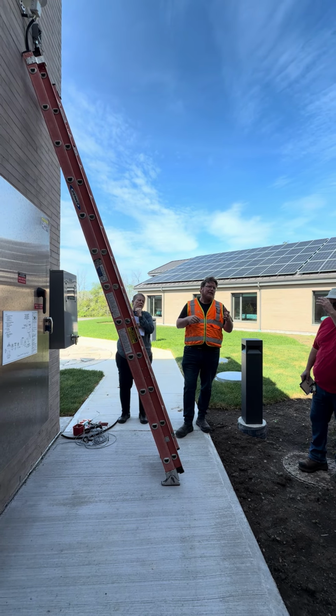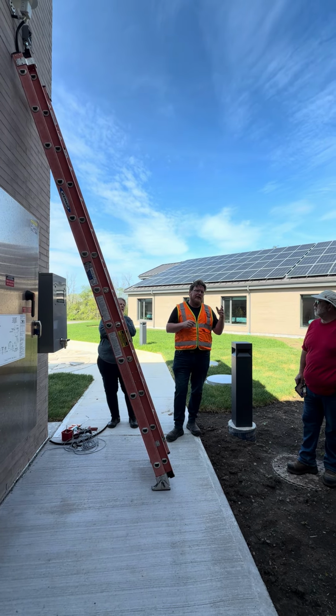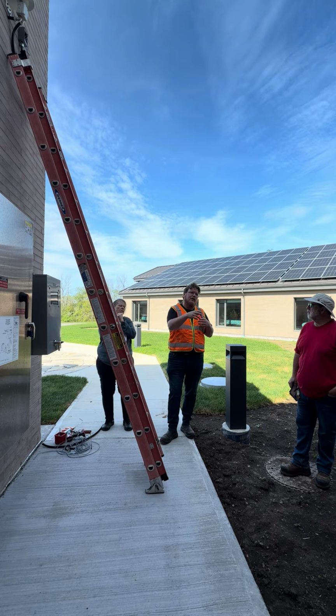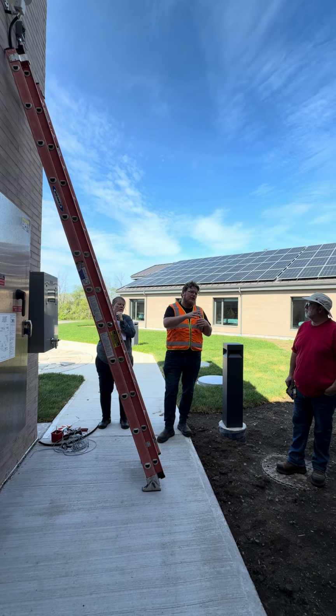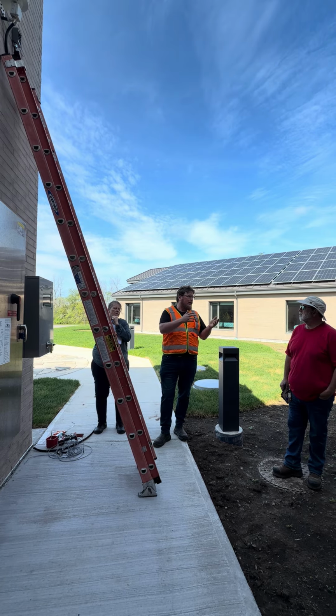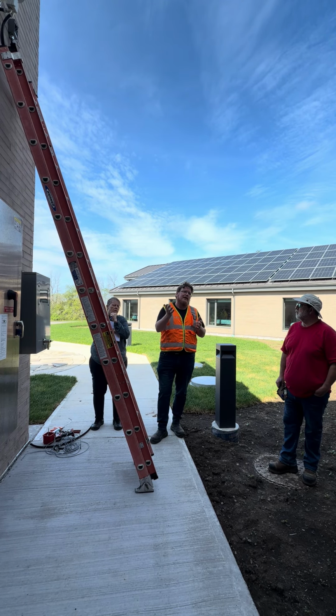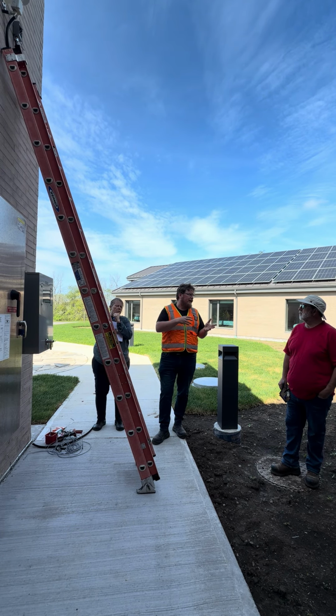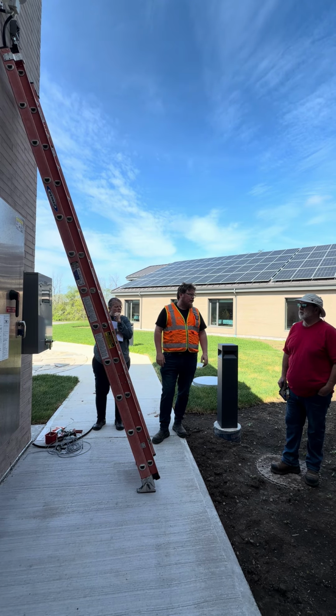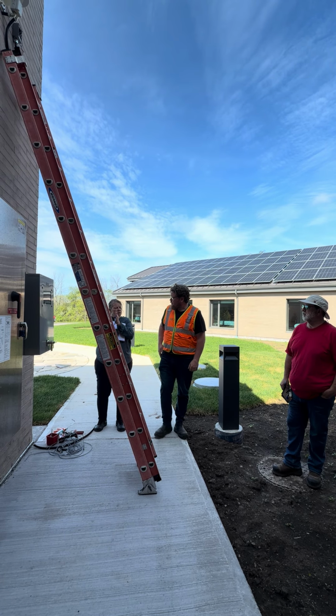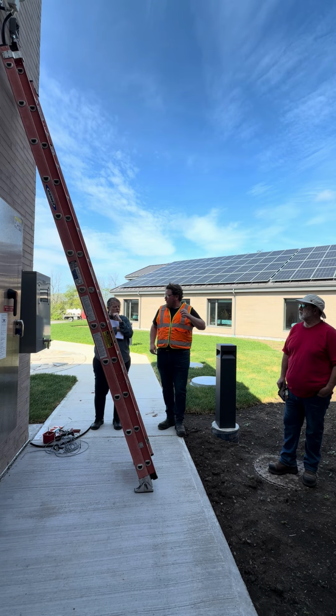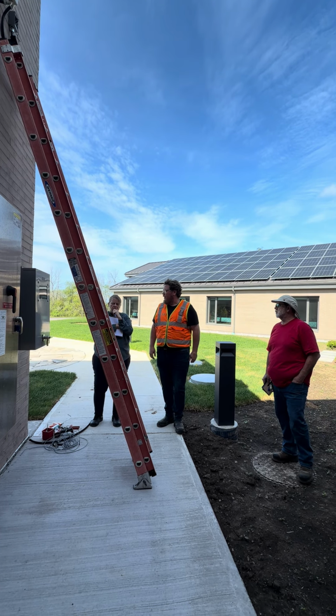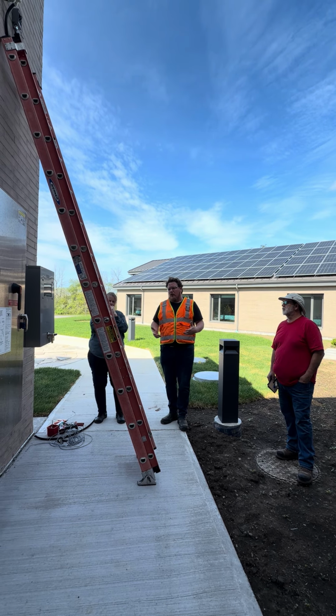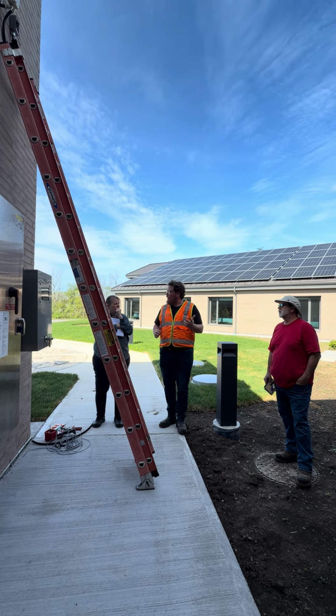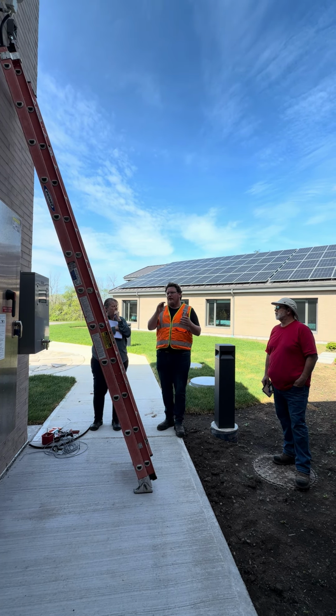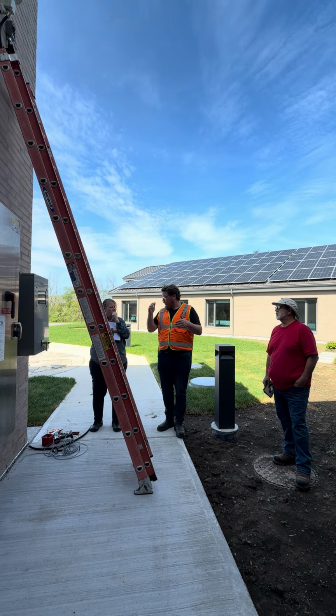There's some upgrades that are happening, like the substation right now, the Marysville one, is on a temporary substation, so they're going to have to transfer the loads over sometime in June or July, and we can work with you on what's involved. It's pretty easy, but we have to coordinate with them once they've done that transfer. They want to retest that transfer trip. So basically, it's not overloading the outlet to the street, right? Yeah, it's not overloading at their substation. So if there's a drop in load, and all of a sudden there's too much generation, the voltage is rising too high at the substation, they can dispatch and turn off the solar to reduce that.